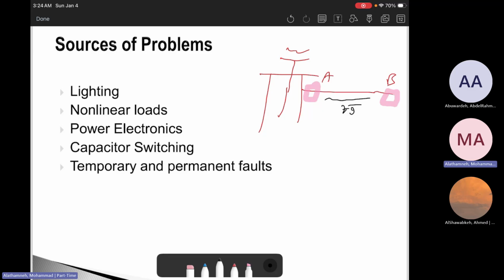The other thing, in low voltage, is the widespread use of low cost electronics, like LED light bulbs. Those are cheap and very energy efficient. Phone chargers, TVs, receivers, low quality UPS (uninterruptible power supply) units can draw distorted currents. This can inject harmonics into the network, and renewable energy systems as well can have low ride-through capability. So this can create power quality issues, and those devices are very sensitive to them as well. As I said, power electronics are a cause of power quality problems, they can also be the victim of power quality problems, and they can also be the solver of power quality problems.